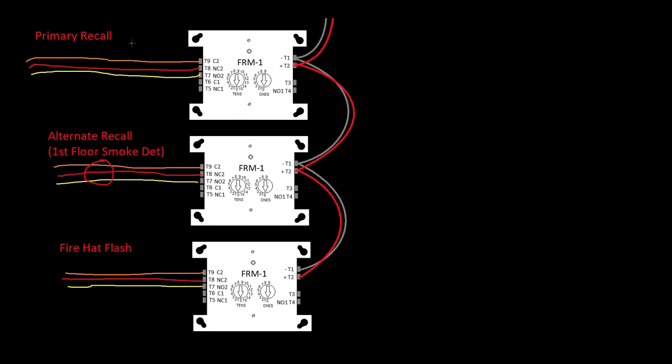And most of the time they're going to be confused by that question because they are they're used to working on their equipment. So they're going to be like 'what are you talking about, you can't send me two relays,' or they're going to say 'well you have to, you also have to give me the primary, because if you just give me the fire hat then how's my elevator going to,' you know, they're going to think you're stupid. But it's because some equipment can only handle one signal and some equipment needs that second clue of where to go.